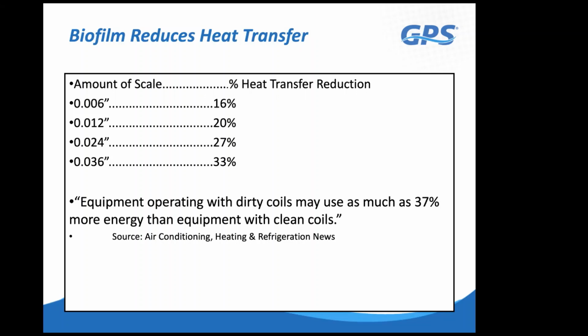Some of these coils that I've seen in the field, visually, they look great. They look clean on the surface, but if you actually cut that coil in half and look at a side profile view, from years of power washing the coils, you've compressed a lot of that biofilm right into the center of the coil, so visually you can't see it. It's hard for the UV lights to even get into it, especially into a deep coil. So that's why this ionization before the coil is nice. It goes through the entire depth of the coil and treats the entire depth of the coil.